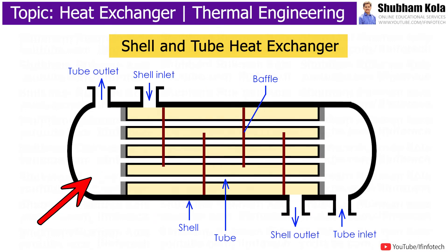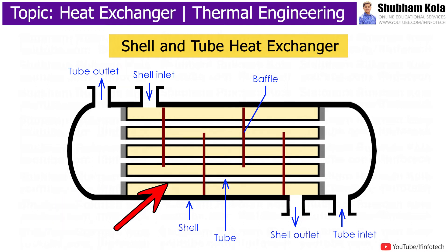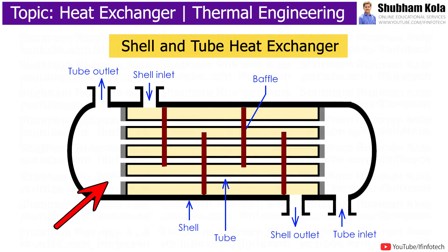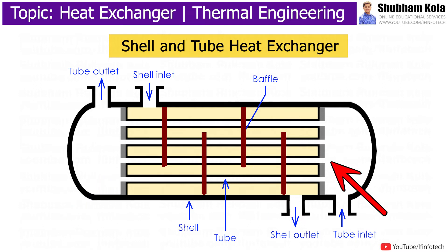Shell and tube type heat exchanger is designed with a number of tubes placed inside the cylindrical shell. All the tubes within the shell are collectively termed as tube bundles. Each tube passes through a series of baffles and tube sheets. One of the tube sheets is fixed and one is free to move.